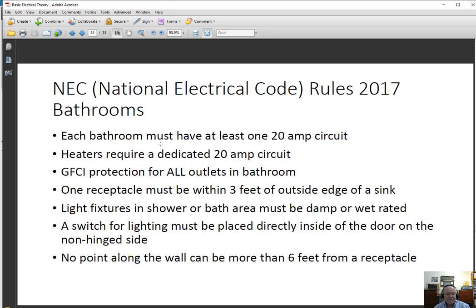Now we go to bathrooms. Every bathroom in your home must have at least one 20 amp circuit. If there's a ceiling heater — the kind where you walk in and there are three switches for fan, light, and heater — the heater itself must have a dedicated circuit separate from the fan and light. GFCI protection is required in all outlets in the bathroom, not just those within six feet. So even if receptacles are nine feet away from water, if they're in the bathroom, they must be GFCI protected.